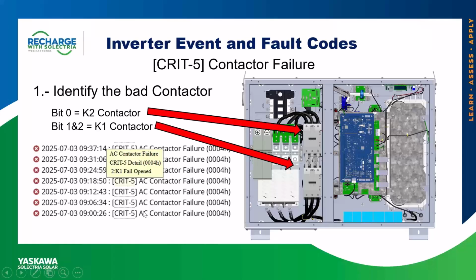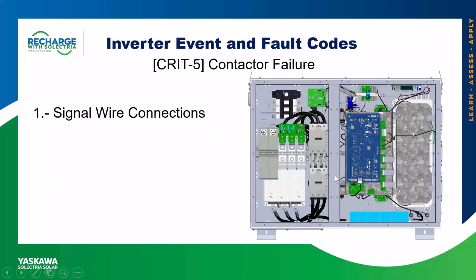So once we've identified which contactor is causing the issue, in this scenario K1, the bottom one, what we need to start off with is check the signal wire connections. You're going to notice on the right-hand side of each contactor, you have some signal wires. These signal wires are coming directly from your DSP board, which stands for Digital Signal Processing board. This signals the contactors with a signal voltage of approximately 24 volts DC to allow the coil inside of the contactor to close in and then allow the full voltage to pass through.